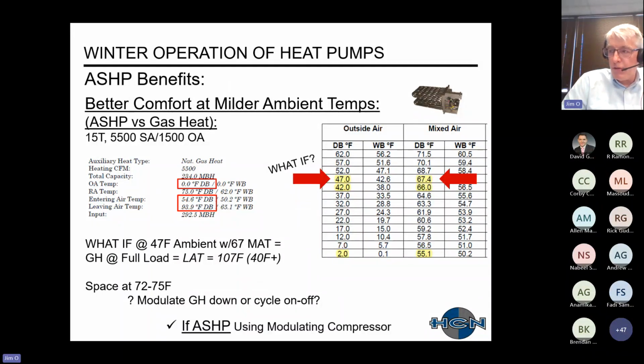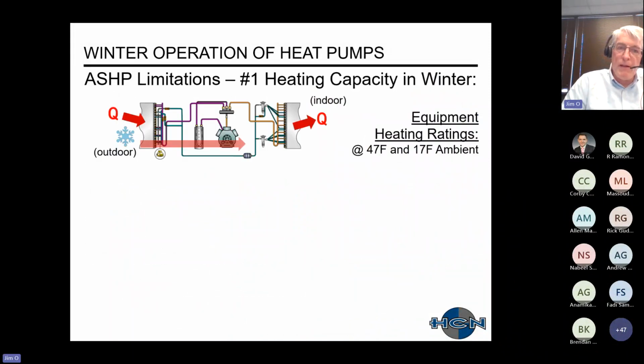But if you do have an air source heat pump, you'll be able to have a modulated compressor, whether that modulating compressor is a digital scroll or a VFD. You'll be able to accurately dial in your leaving air temperature to your space temperature to once again improve your comfort conditions in your space.